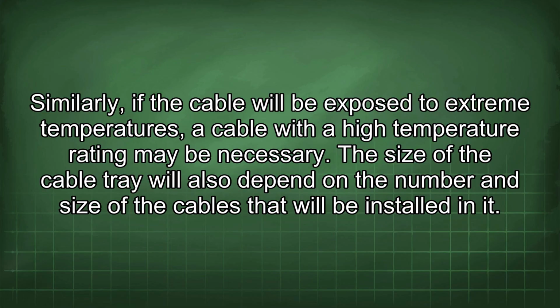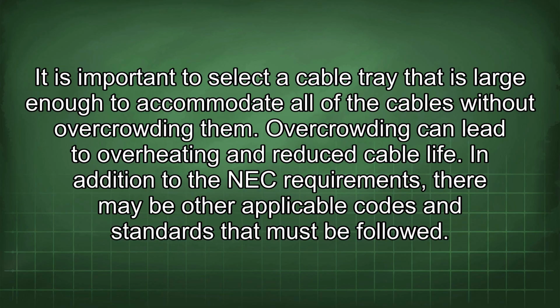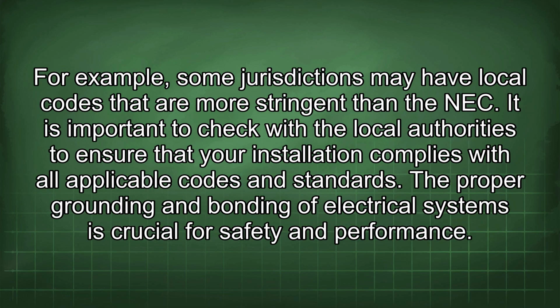The size of the cable tray will also depend on the number and size of the cables that will be installed in it. It is important to select a cable tray that is large enough to accommodate all of the cables without overcrowding them. Overcrowding can lead to overheating and reduce cable life. In addition to the NEC requirements, there may be other applicable codes and standards that must be followed. For example, some jurisdictions may have local codes that are more stringent than the NEC. It is important to check with the local authorities to ensure that your installation complies with all applicable codes and standards.